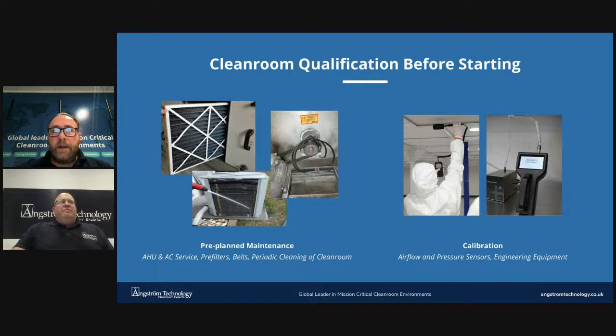So before we even discuss the actual validation methods of a clean room, there are two other important areas to consider. Firstly, if you are having an engineer come to your facility for testing, let's be honest, the only thing that concerns you as production manager or quality assurance team is that pass or fail comment at the bottom of your report. There are pre-planned courses of maintenance that you can undertake to ensure this runs as smoothly as possible. If it's an AHU system, check the belt alignment, belt tensions, change panel and bag filters, check your AHU frequencies are all very similar to the last visit recorded. For an AC unit on the system, regular servicing and cleaning of coils, and of course, regular cleaning and maintenance inside the actual clean room. All of this can be the difference between a pass and a fail. Nobody wants to fail because this causes downtime in production.